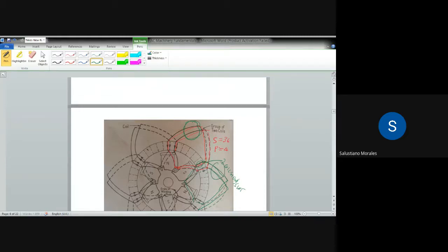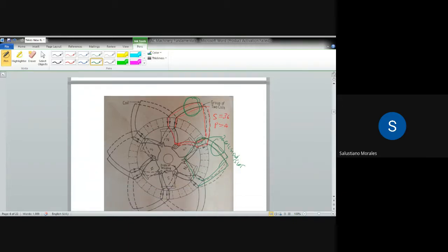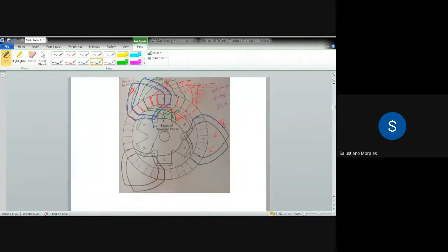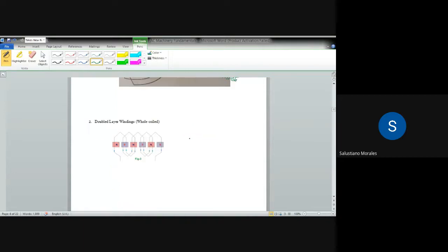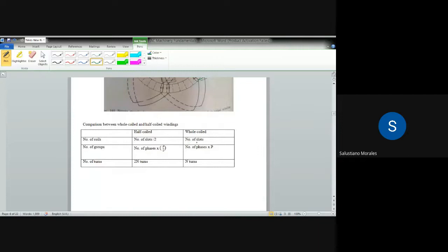The coils found in one pole per phase are called a group. In this whole coil illustration, there are two coils per group, and for phase A alone there are six groups. For a three-phase machine, total groups equal 18. In the single layer arrangement, there are three groups per phase, giving nine groups total. The double layer has significantly more groups than the single layer.